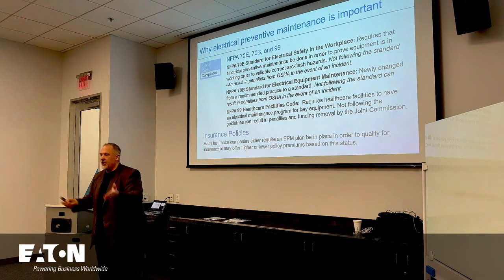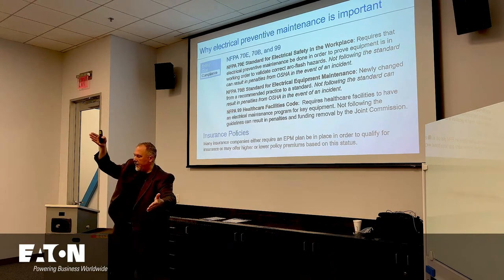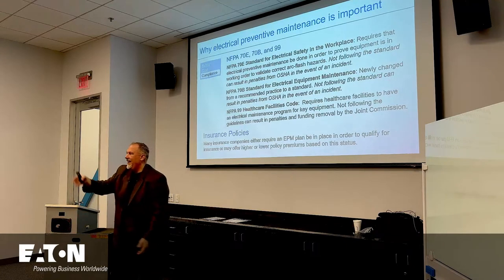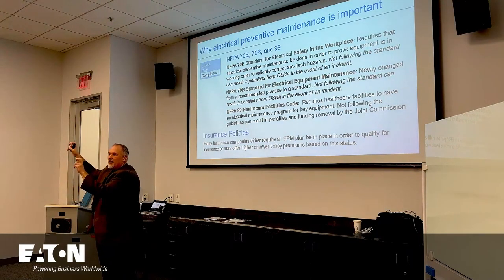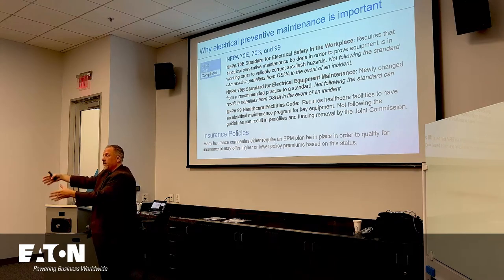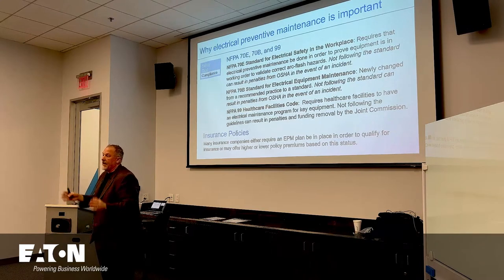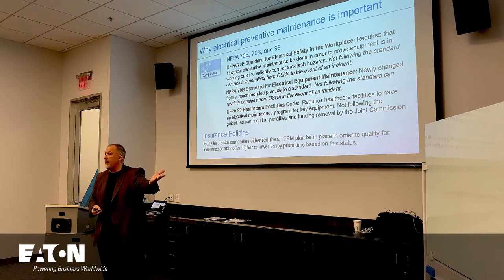So you had the trilogy of installation requirements, safe work practices, and this recommended practice on maintenance. The shift had to occur, I'm surprised it didn't happen sooner than this cycle, where maintenance became a mandatory requirement instead of a recommended practice. That's basically filling out that trilogy, because if 70E says it has to be maintained, how are you showing that it's maintained?